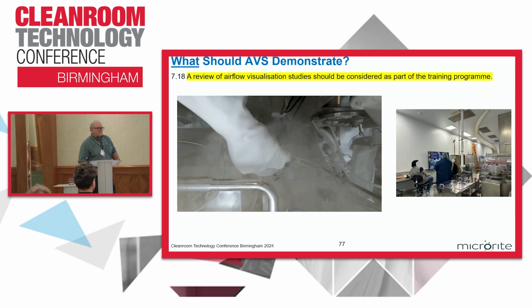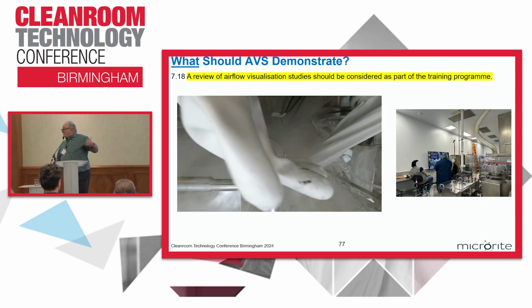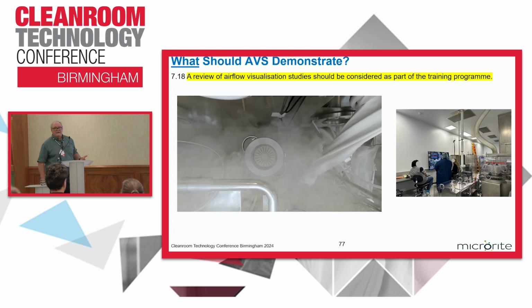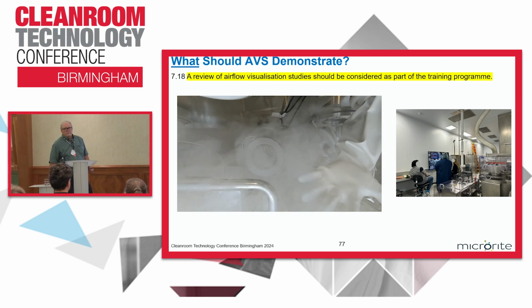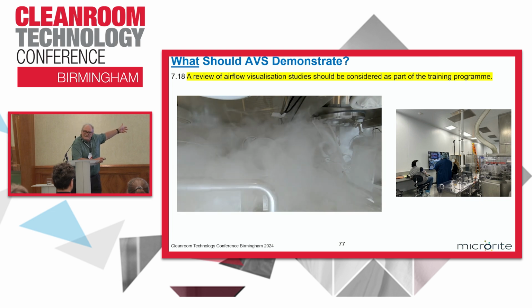The aseptic experts I work with think it's a problem. The customer didn't think it was a problem. They thought, well, what's the matter? Right? There's no plate there yet. Well, the plate should be there if you're doing an aseptic connection, shouldn't it? Of course it should be. You should be monitoring it.